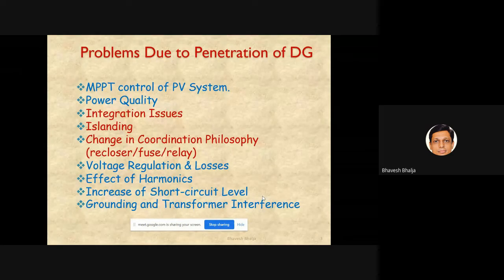The next issue is related to voltage regulation and losses. We know that at distribution level, voltage regulation plays an important role, right? And that is the fundamental difference: if I have a distribution network, the percentage voltage regulation should remain within plus or minus 5%. Whereas if I am calculating voltage regulation at transmission level, then I think it may exceed 10% also, right? There is no harm in that, because at transmission level efficiency is more important, right?